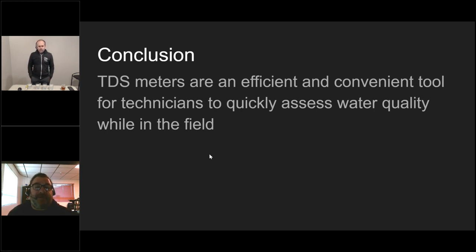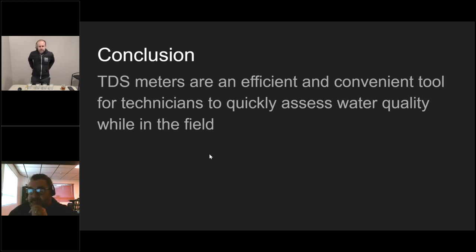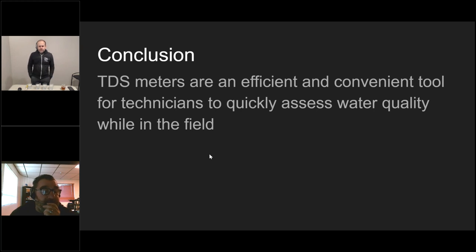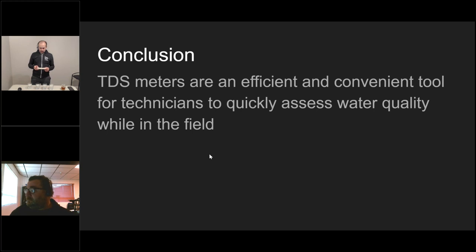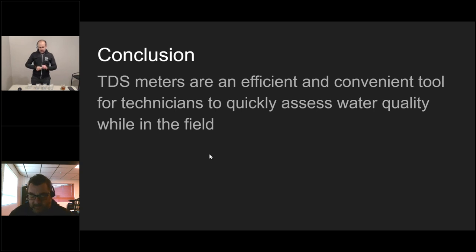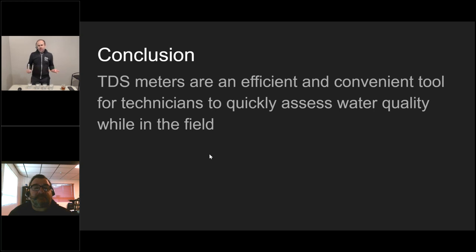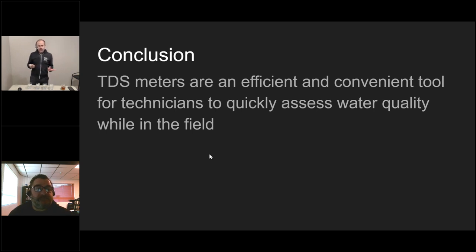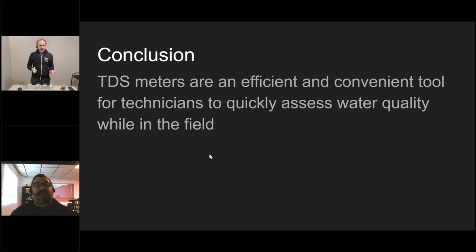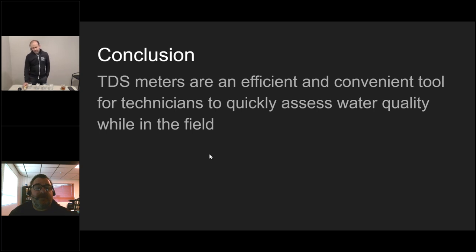Would you mind putting together a list when you put it on Facebook and social network, just like what you recommend? Absolutely. Somebody asked what the meter was that you're using. This is an Oakton TDS tester low. It's a real basic temperature compensated meter. Like I said, it has an adjustable factorization. You can actually just move the factorization up and down with a couple of buttons. People will probably be surprised to see that it actually only reads down to in 10 increments, 10 parts per million. It doesn't read down to single digits, but it's not really necessary for what we do. Most meters you're going to buy today are going to have a larger display and they'll probably read down to one point indexes. A little bit more accurate or more precise, I would say. If you're showing it to a customer, they might have a little more confidence in it. Realistically for what we're doing, it doesn't really make that much of a difference.